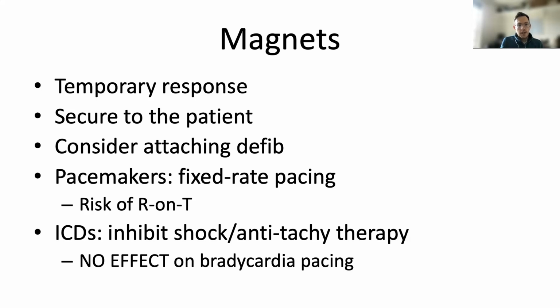And it lays out what the device will do in response to the magnet. So if it's just a pacemaker with no defibrillatory function, the magnet application will put it into a fixed rate pacing mode. The benefit of that is that it's not looking for any cardiac stimulus, so it won't do anything in response to diathermy or other interference. But the potential theoretical downside is that you have the risk of the R on T phenomenon where it tries to pace on top of a native beat. But it's thought that the risk of that is low in practice.